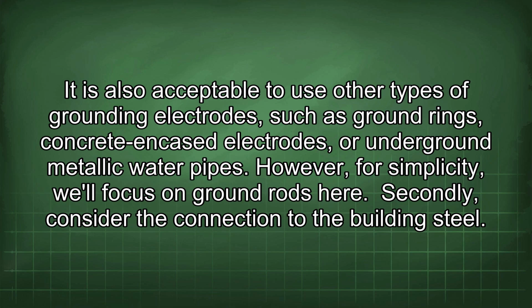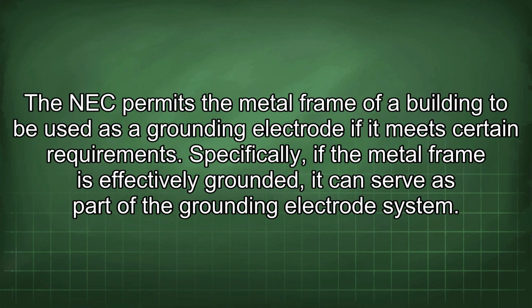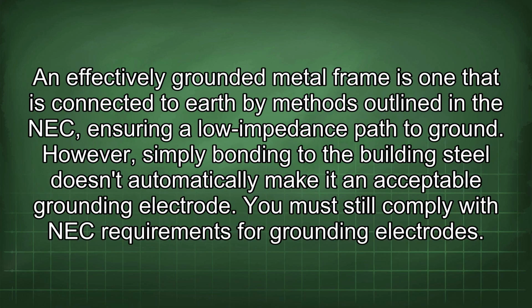Secondly, consider the connection to the building steel. The NEC permits the metal frame of a building to be used as a grounding electrode if it meets certain requirements. Specifically, if the metal frame is effectively grounded, it can serve as part of the grounding electrode system. An effectively grounded metal frame is one that is connected to earth by methods outlined in the NEC, ensuring a low impedance path to ground. However, simply bonding to the building steel doesn't automatically make it an acceptable grounding electrode. You must still comply with NEC requirements for grounding electrodes.